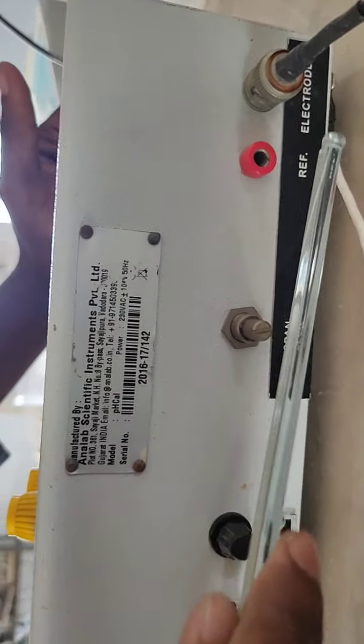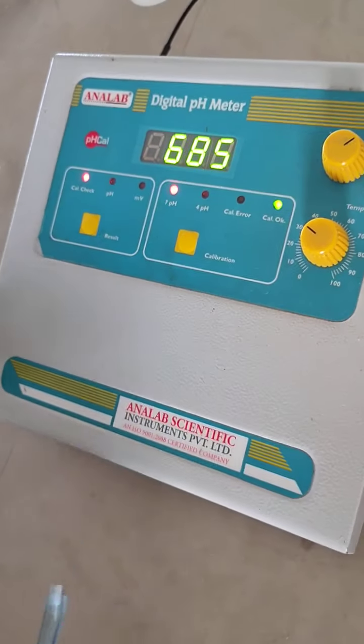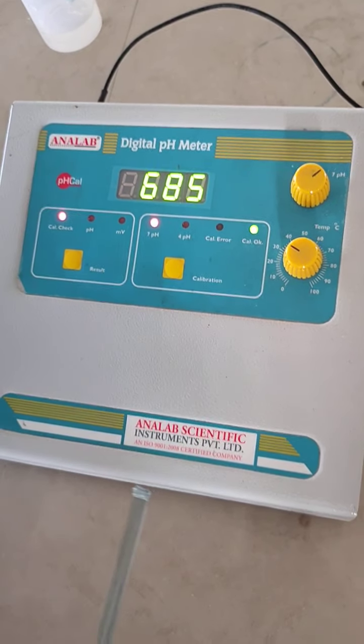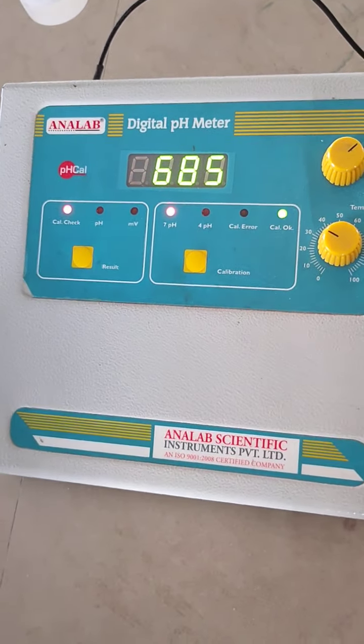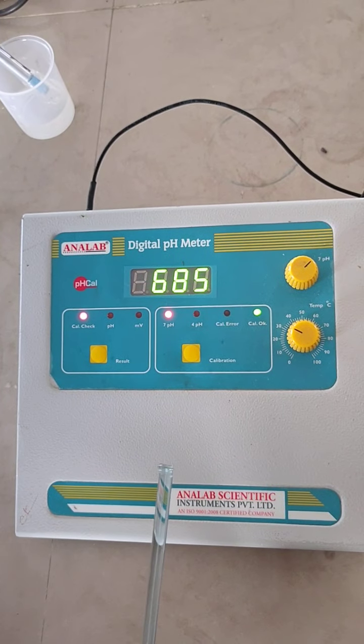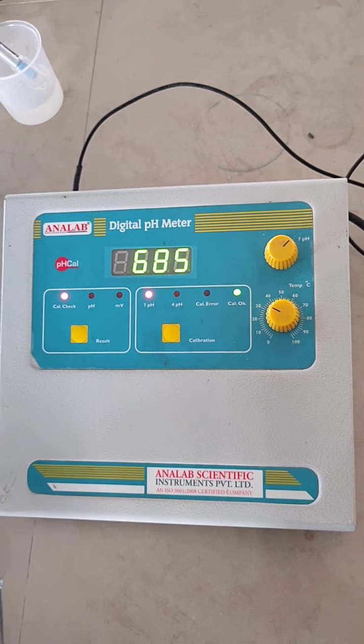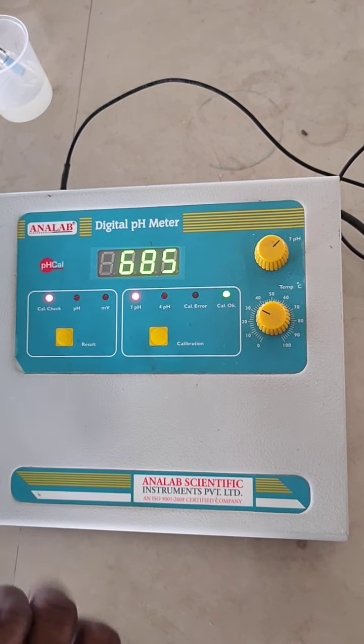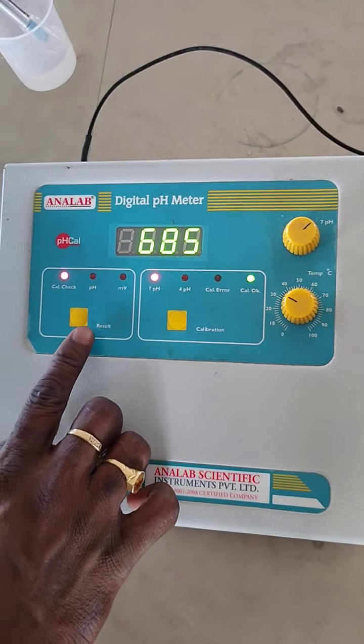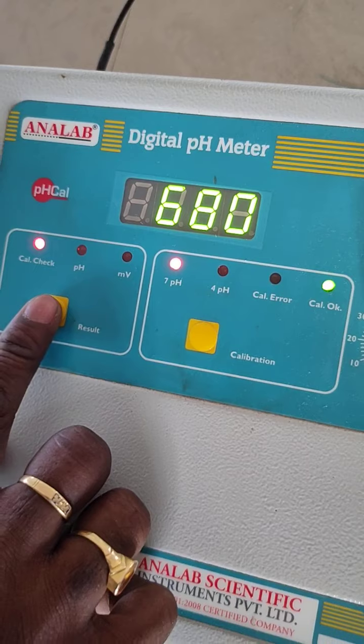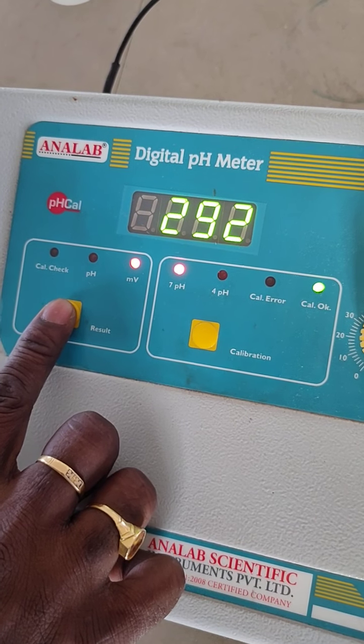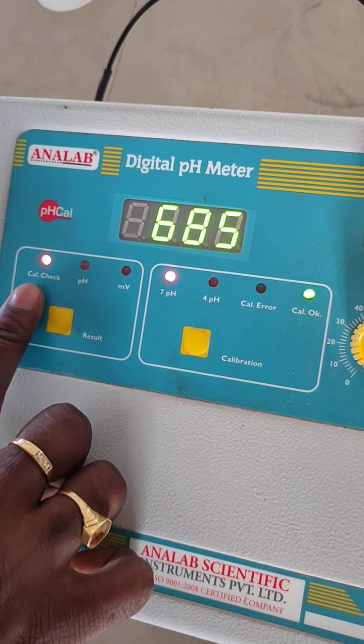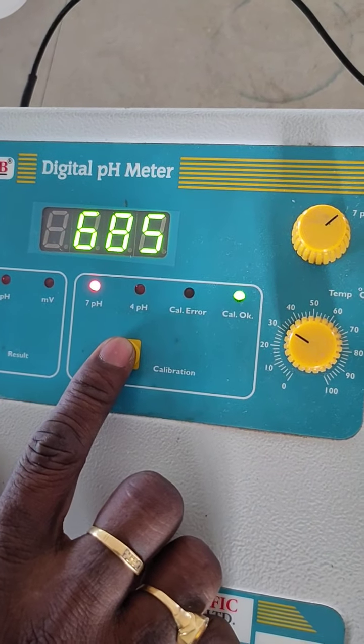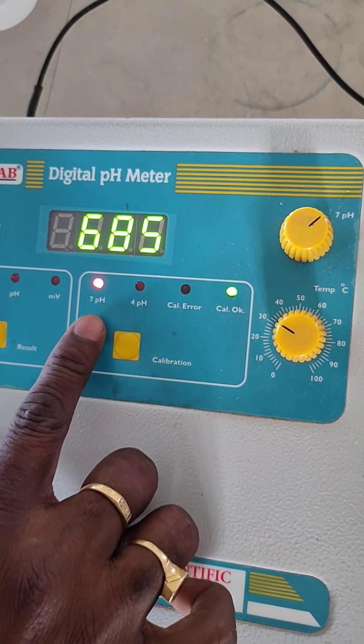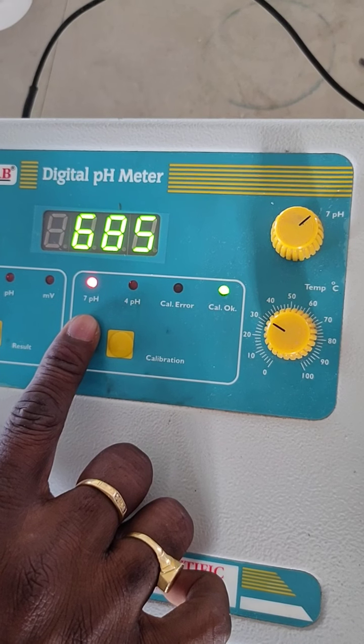Okay, so these two are probes for putting electrodes. One is the reference electrode and another one is the indicator electrode, the glass electrode. Here only the glass electrode is sufficient, no need of attaching a reference electrode. So let us see how the instrument is calibrated by using buffer solutions. Okay, first you put the result part in calibration check. See here, it changes color when you press. Then put the calibration part in 7 pH first, because 7 indicates neutral medium and is calibrated first.